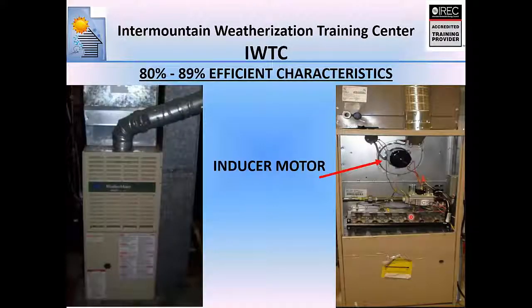All right, the other thing, we talked about inducer motors. Anything under 80% efficient does not have an inducer motor and falls into that 60% category. Again, we've got the louvered door still, because combustion air has got to get to the burners through that louvered door. But now notice the big draft hood is gone. We still have a metal flue, so that's a giveaway as to what efficiency range it falls in. But now we have an inducer motor.